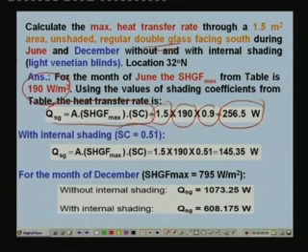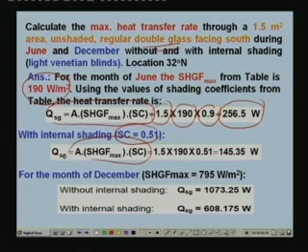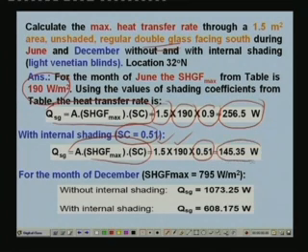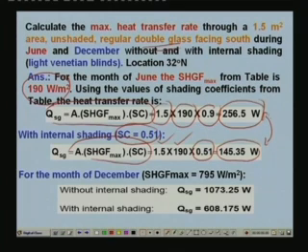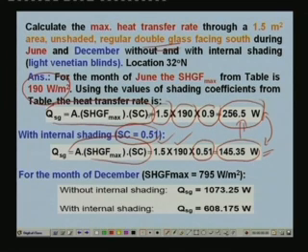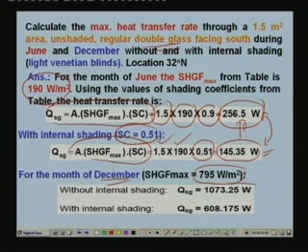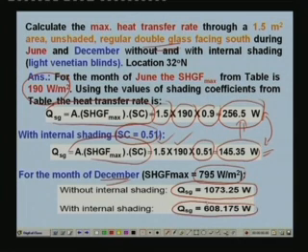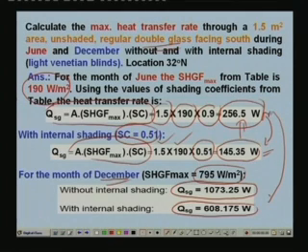With light Venetian blinds (SC = 0.51), Q = 1.5 × 190 × 0.51 = 145.35 W. With Venetian blinds you reduce the transmitted energy by almost 50% compared to without internal shading. For December, SHGF_max = 795 W/m². Without internal shading, Q = 1073.25 W; with internal shading, Q = 608.175 W. The south-facing glass transmits much less energy in summer than in winter.